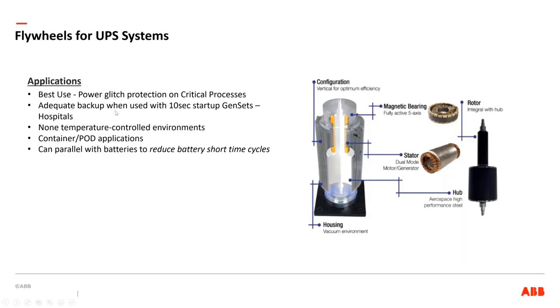On the flip side, it's not a cheap solution. I think I have a later slide comparing that. With a 15-second solution versus a 5 or 7 minute battery, the 15-second solution is still significantly more expensive. The short backup time is a concern. Data center facility managers are not comfortable with that. In a hospital setting, where the generator is required to be up and running in 10 seconds, they seem to be a lot more comfortable with just having that 15-second gap filler or protection while the generator starts. As I mentioned, there are not a lot of manufacturers of flywheels out there.